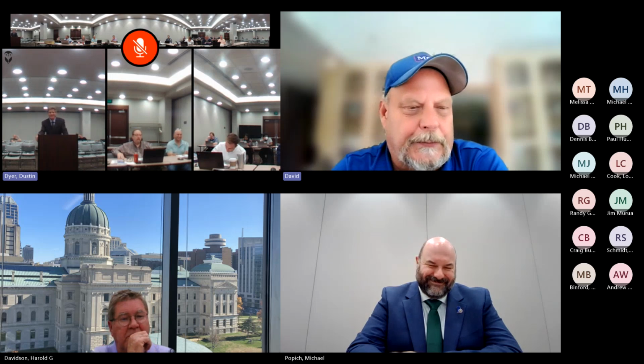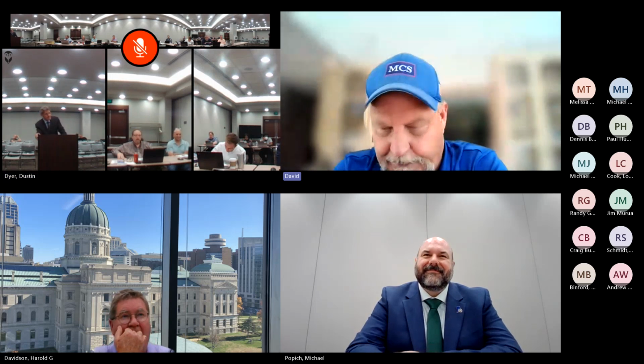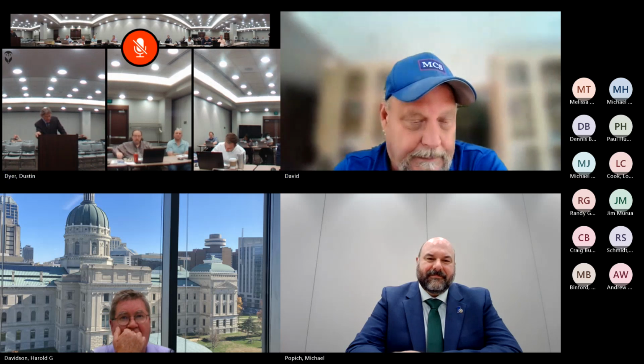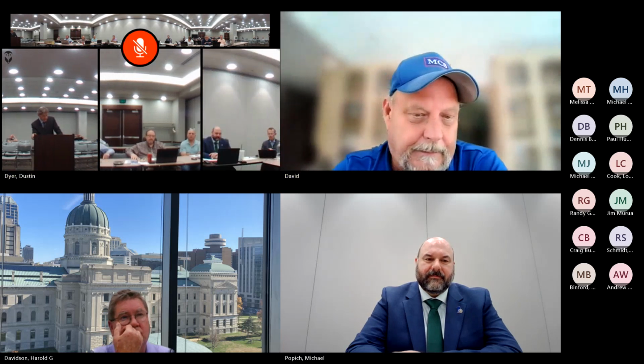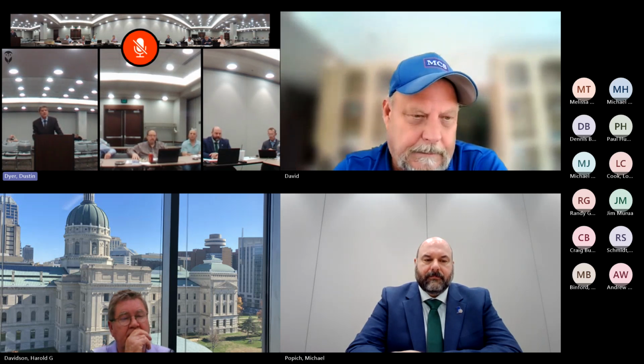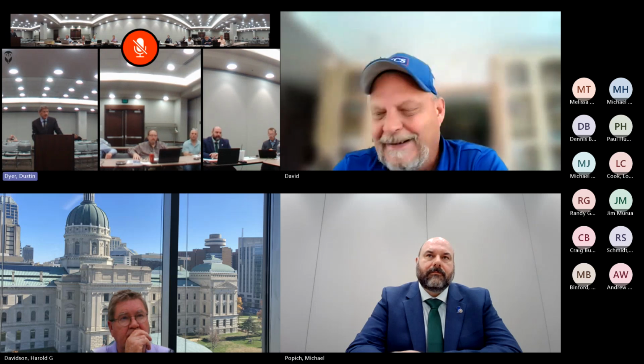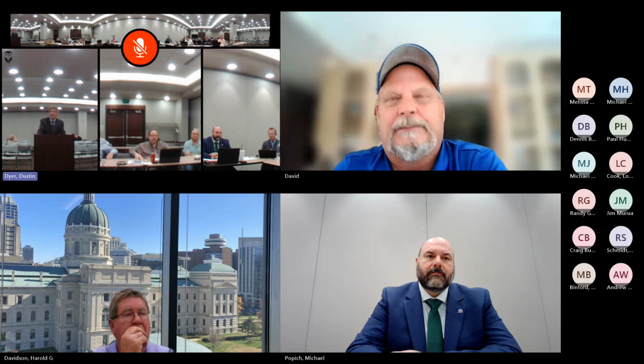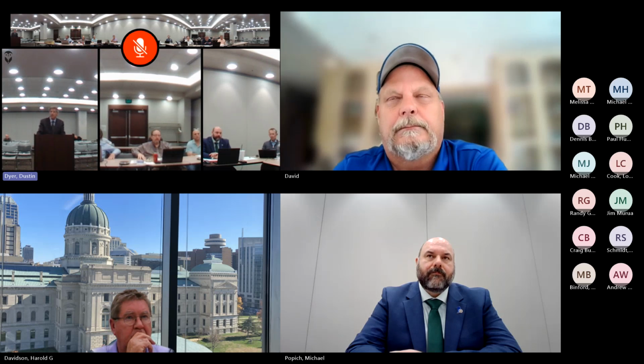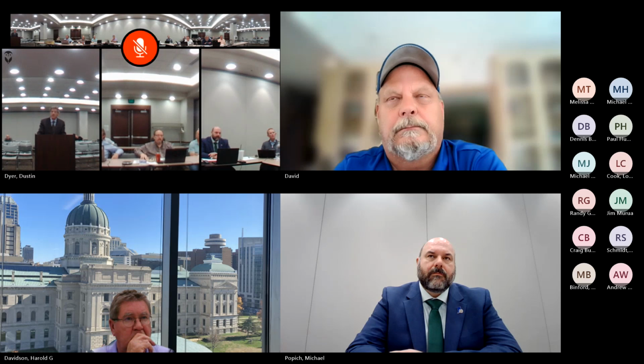But you're going 4 stories without a fire rated chase. That is your question, right? That is correct. That's the second variance request, because we have 4-story open stairs in the unit. The code allows that, but technically it doesn't allow this because it's concealed, so to speak. I think you still need the fire blocking between each floor. We do, I absolutely agree with that, because otherwise you've got an interconnection of horizontal and vertical spaces. You're going to get some containment in there from floor to floor within that cavity. A very important point. I should have included a variance.